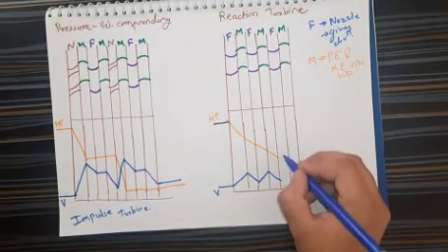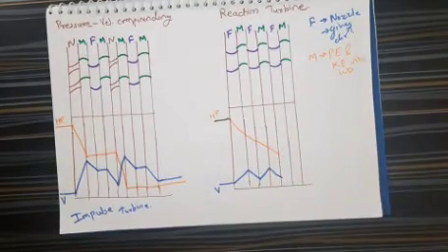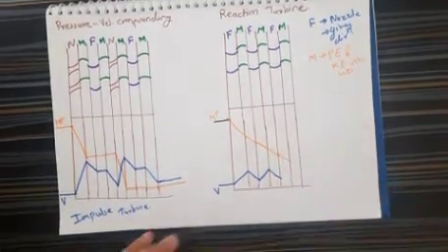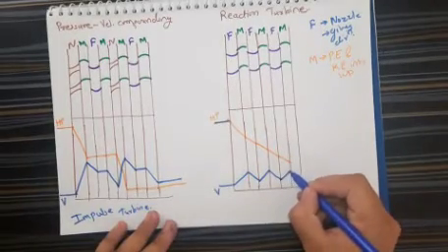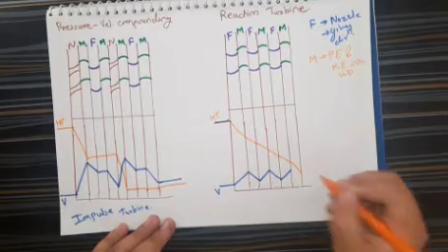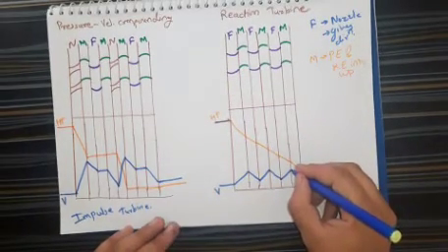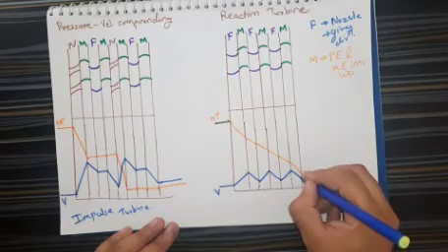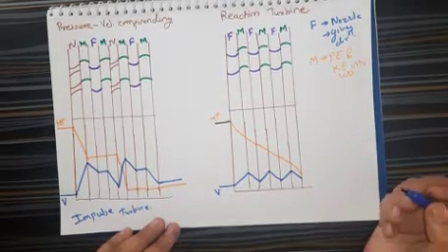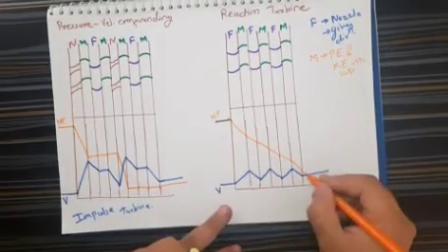Similarly, again on a fixed blade, this pressure energy drops down and will be converted into kinetic energy, and on the moving blade again the pressure drops down and is converted into work done, along with the drop in kinetic energy converted into work done, and here will be the exit.